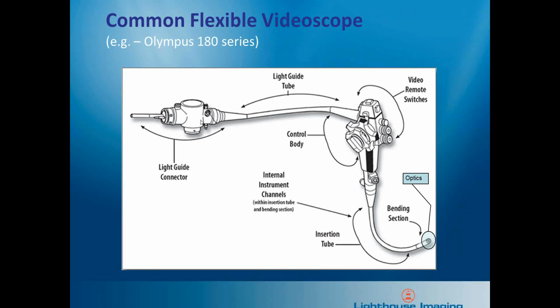On the left end over here, we see the interface to the processor tower system. Fiber optic illumination fibers go through there into the control body. Typically, there will be controls for both horizontal and vertical articulation of the tip. There may be remote control switches. There may be access ports for working channels, followed on the lower right of this image by the insertion tube. This is the length of the scope that's inserted into the body.